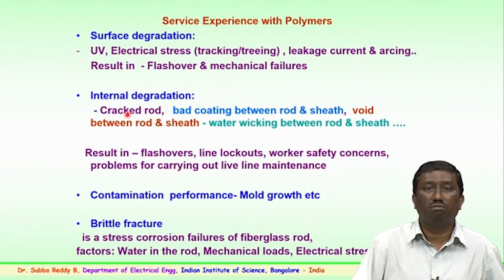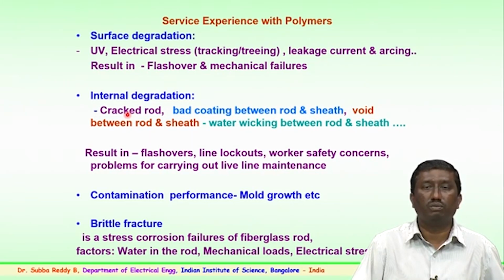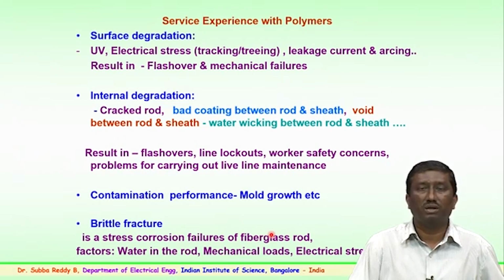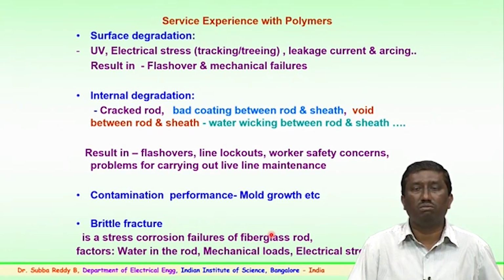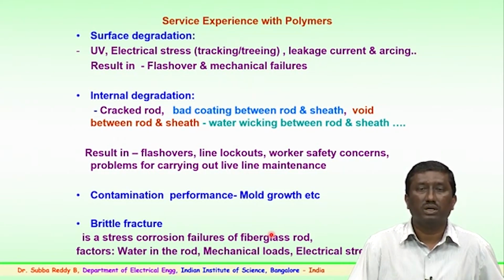So, the result is flashovers, sometimes temporary or continuous, line lockouts or blackouts, or the line may give way. So, workers' safety concerns are very important. In case of failures, it should not lead to safety concerns, particularly for our people who are carrying out live line maintenance. So, it is very important that internal degradation and surface degradation are seen and addressed. And contamination performance: initially, polymers are much better when compared to ceramic or porcelain for short term performance, but later on there are reports that mold growth has happened on the surface, and whether this mold growth is likely to create a problem with the insulator. A lot of studies have been carried out on these aspects. We will be looking into the failures where there are problems related to this.